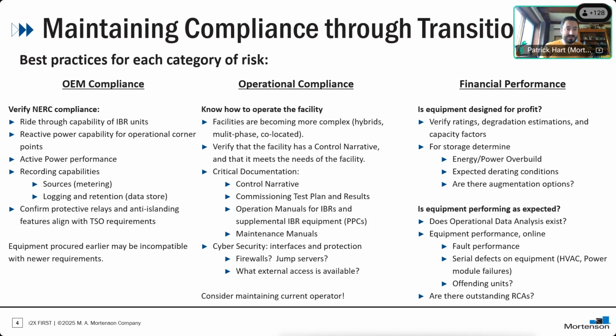So compliance generally impacts your financial performance. If the equipment isn't really designed for it, you're going to face unexpected costs later. I would first determine the IBR OEM compliance—all those parameter settings, ride-through capabilities, reactive power performance, and protective relay settings of the balance of plant.